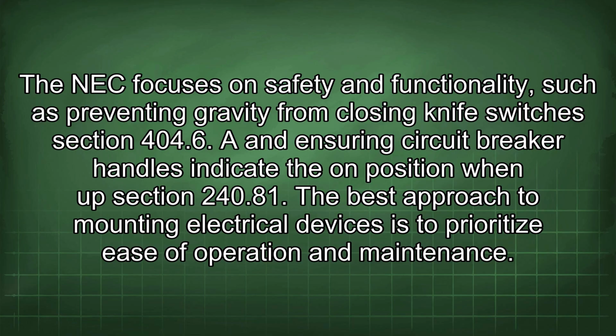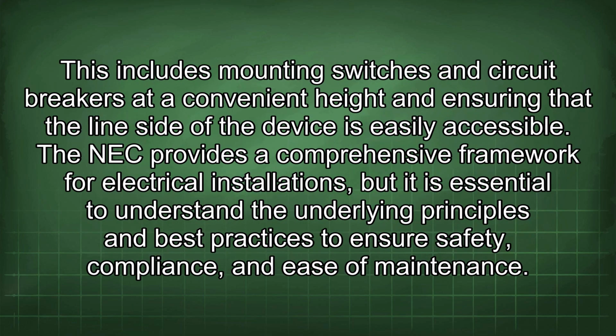The NEC focuses on safety and functionality, such as preventing gravity from closing knife switches, Section 404.6, and ensuring circuit breaker handles indicate the on position, Section 240.81. The best approach to mounting electrical devices is to prioritize ease of operation and maintenance. This includes mounting switches and circuit breakers at a convenient height and ensuring that the line side of the device is easily accessible.